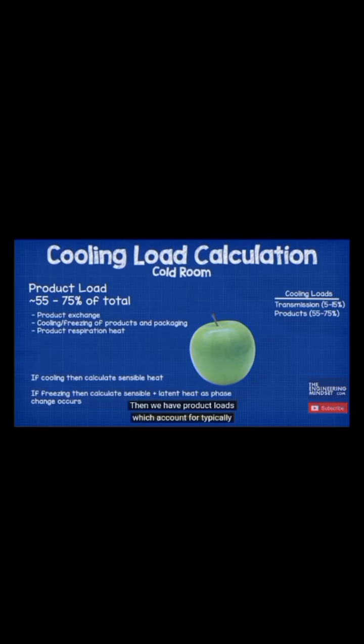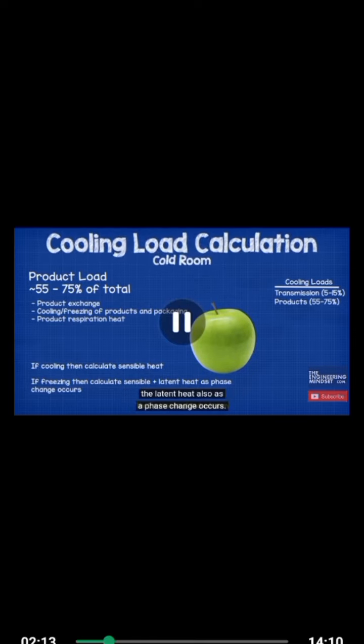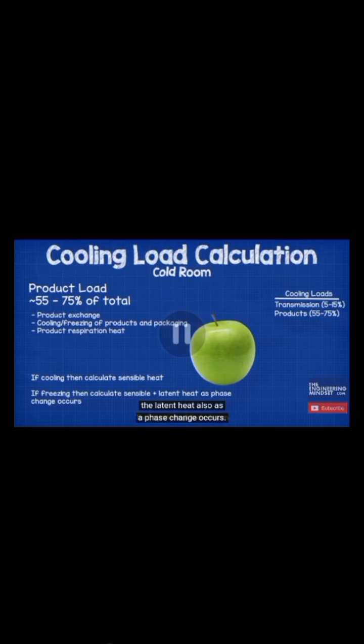Then we have product loads, which account for typically 55 to 75% of the cooling load. This accounts for the heat that is introduced into the cold room when new products enter. It's also the energy required to cool, freeze and further cool after freezing. If you're just cooling the products, then you only need to consider the sensible heat load. But if you're freezing, then you need to account for the latent heat also, as a phase change occurs.